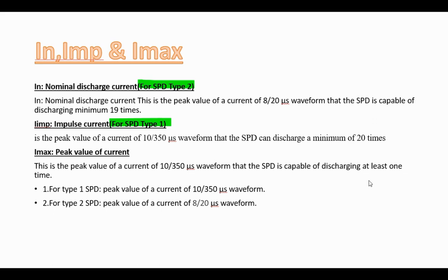Now it's time to discuss Imax. What is Imax? The Imax is the same as the IN for an SPD Type 2 and IMP for SPD Type 1, but here the SPD should suppress these surges at least one time during its whole life cycle.